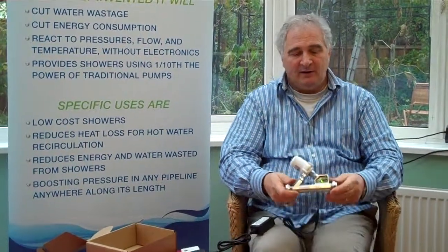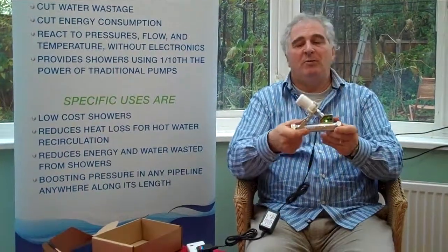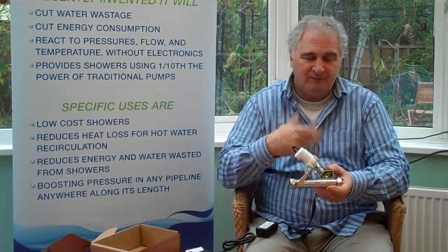When the pump is running, you should get a quick flash — tick tick tick tick. Obviously no noise; that's for your benefit, not the pump's. Those are the three diagnostics. If there's no light at all, then obviously there's no power getting there.